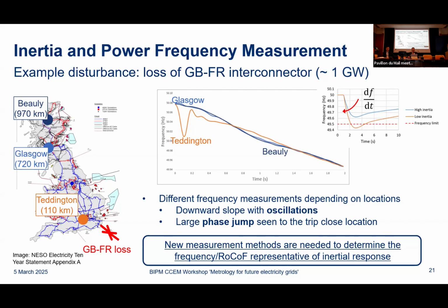And then there was a disturbance on the network. So there's an interconnector between Great Britain and France, and this interconnector suddenly tripped, it disconnected. So a lot of power was suddenly gone, 1 gigawatt, and that caused this frequency disturbance. And what you can see is actually, maybe counterintuitively, the frequency measurements are different across those 3 locations. You can basically see some oscillatory behavior. You can see one very large kind of dip in the orange Teddington frequency line. That's because there's a phase jump that's associated with this type of disturbance.